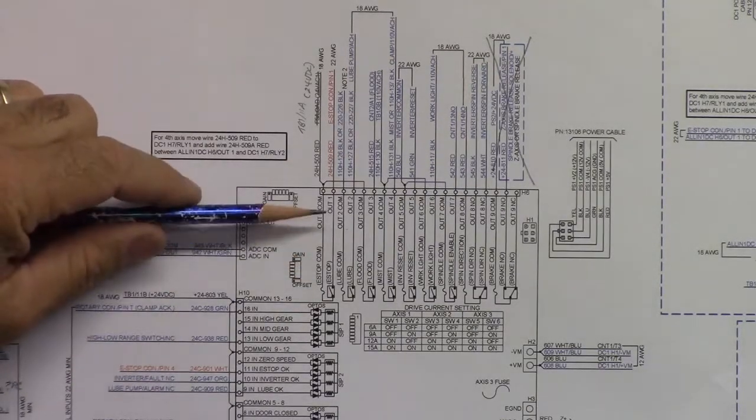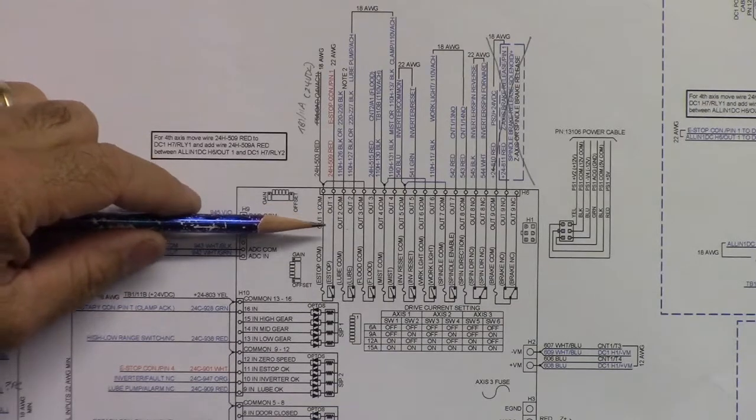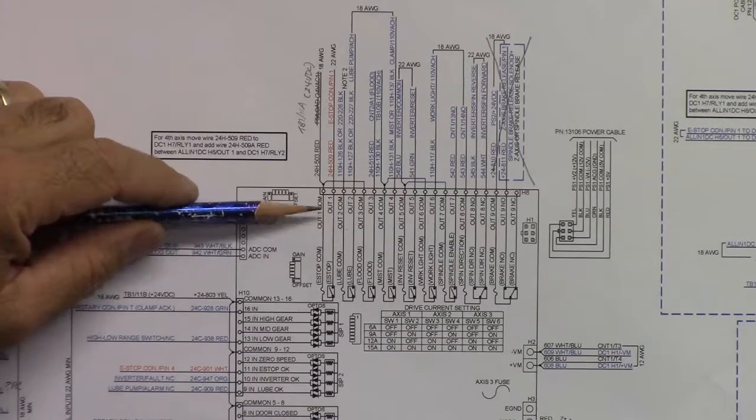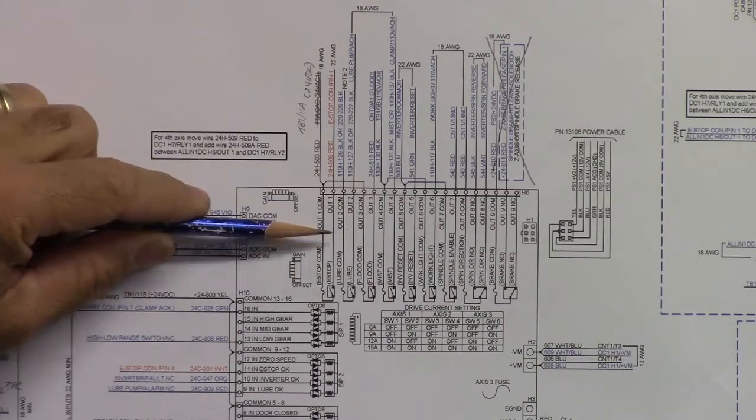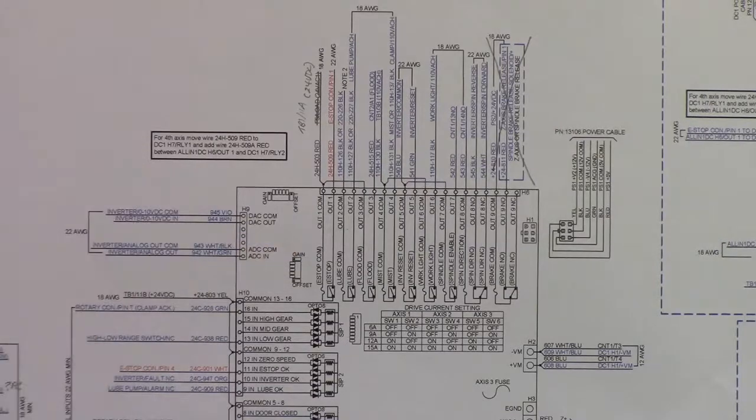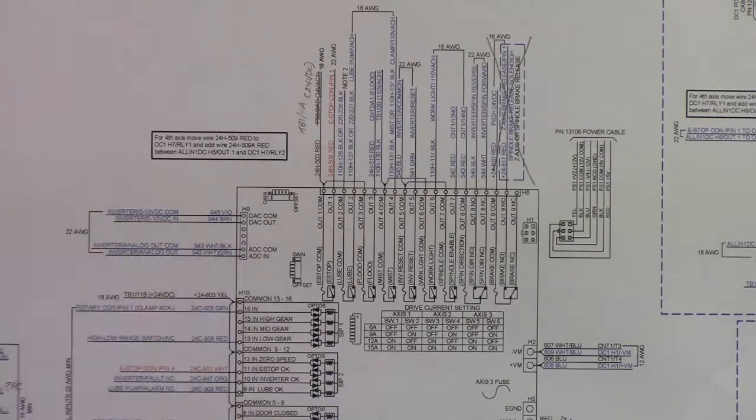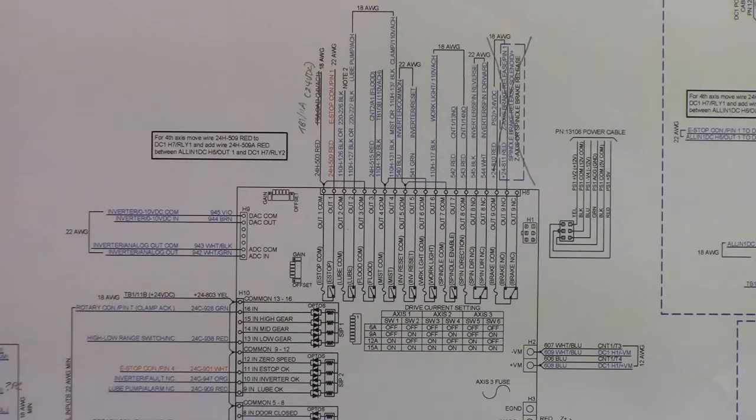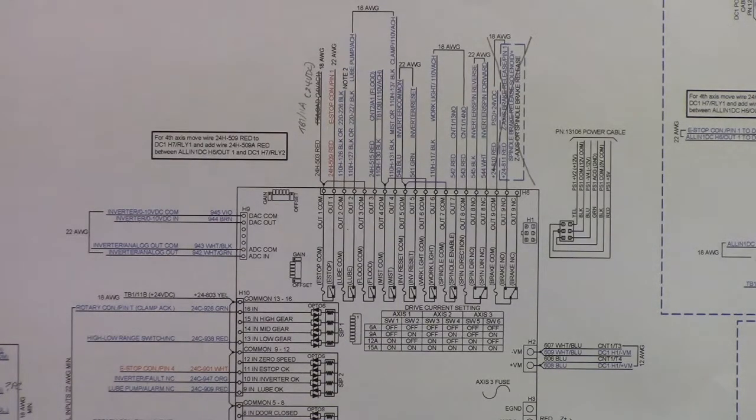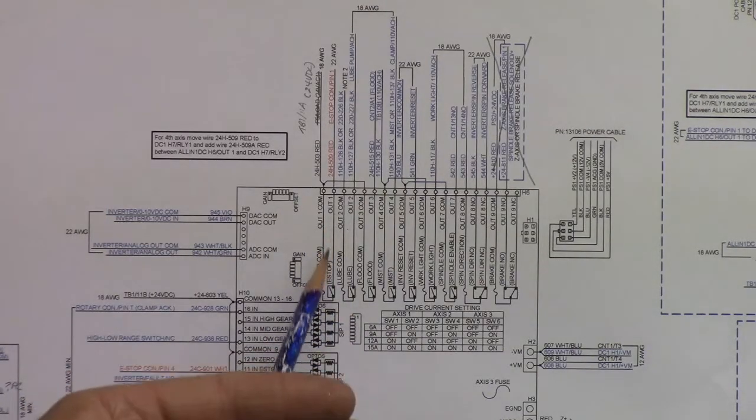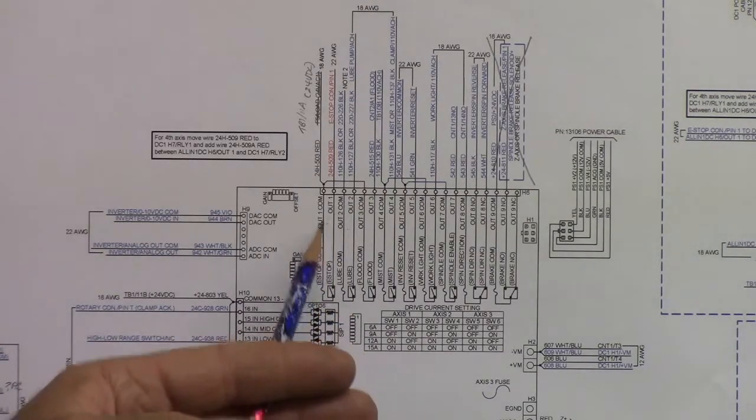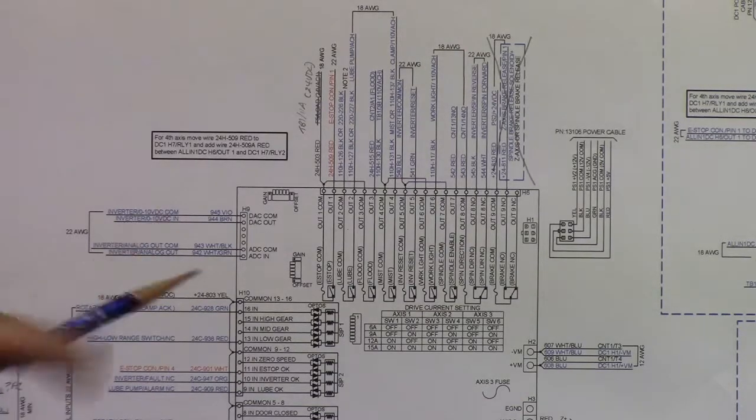The first one is the e-stop circuit. It's basically a relay that if there's a fault, it will open the circuit. This e-stop relay and the e-stop button are in series with each other, and then they go through CNT1. So, if the button is pushed, it opens a circuit. CNT1, our e-stop contactor opens. Or if there's a fault, and all-in-one DC opens this output one, it also opens CNT1.